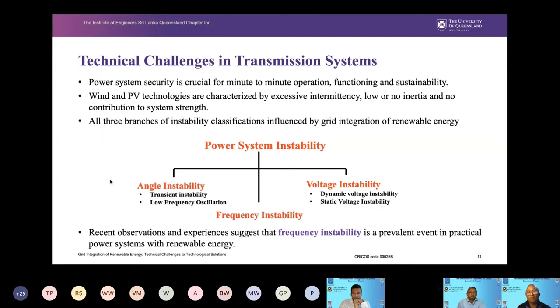Traditionally, power system instability, this is the area I have been working on for the last 25 years, can be classified into angle stability. So we have this magnitude and the phase angle. The angle could get affected, and then there could be an issue called transient instability, losing synchronism, losing power plants one after the other in a cascaded fashion.